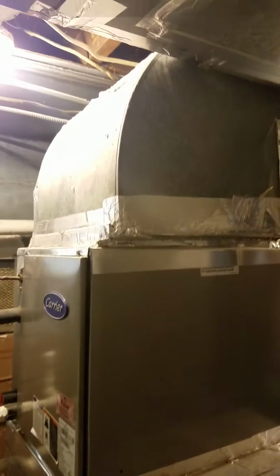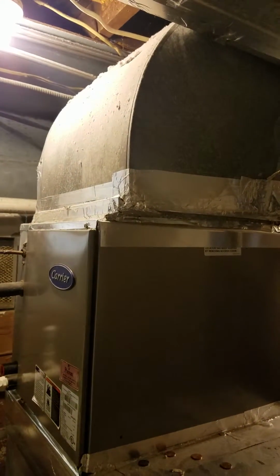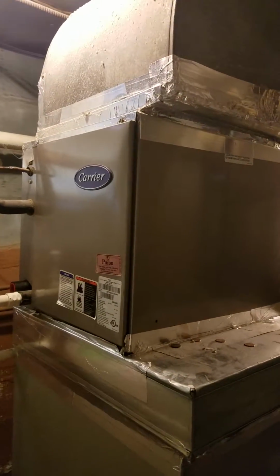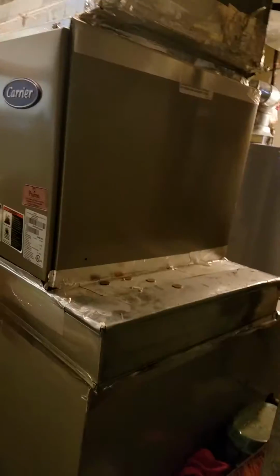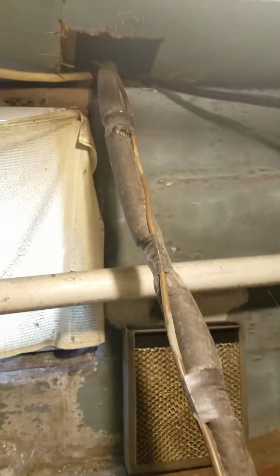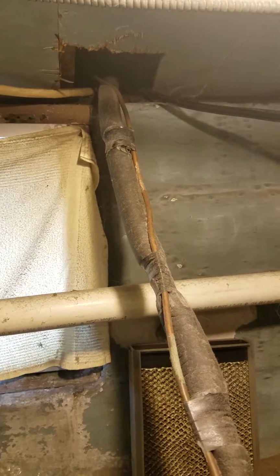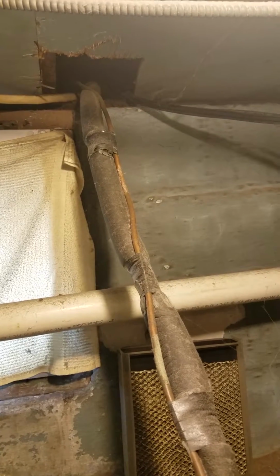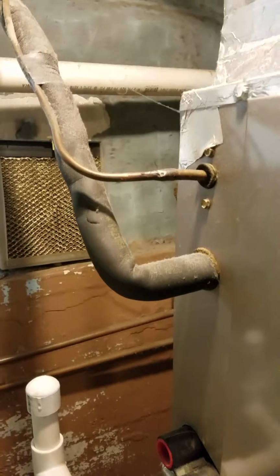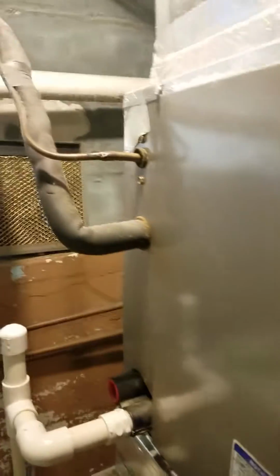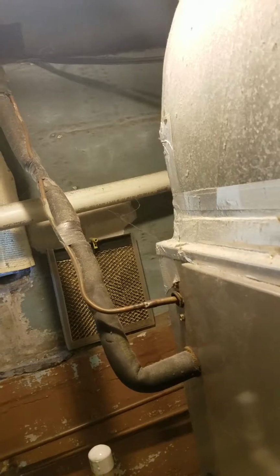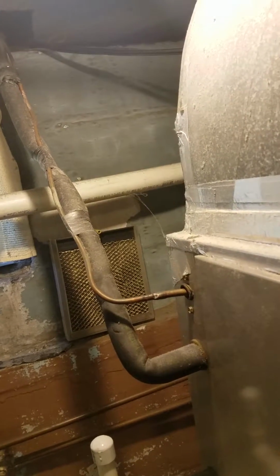Let me go around back here and show you this also. Here's the top of the ductwork in the back. See how that coil's offset again. So really bad, and that needs to be corrected. Refrigerant line going right out that side of the wall. You can probably run your PVC out that side of the wall too, and that way shorter distance, better performance, and approximately about 10 foot of PVC is all we would need then.